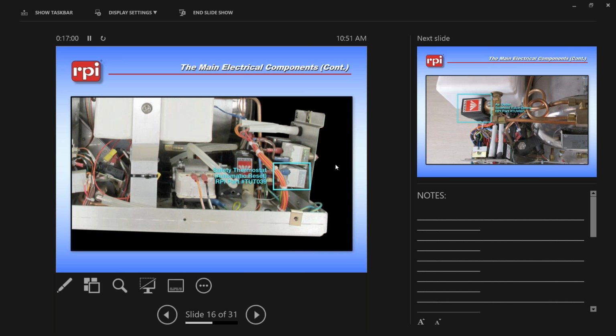Safety thermostats. There's two. This top one that we've highlighted here, this is the manual. It has a little red button on the back. It'll pop out if the unit gets too hot. Now, one of the things that's usually a good indicator that not only this one is being activated is also the one right below it, which is the automatic reset. Now this one's set to go at a lower temperature. So if you're triggering the manual, probably your automatic is not functioning at the same time.